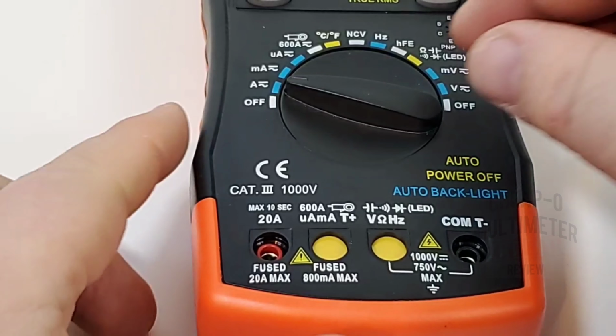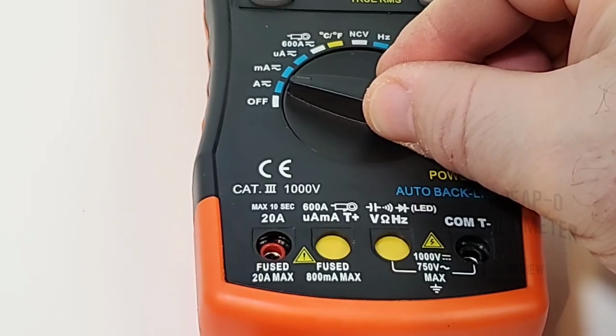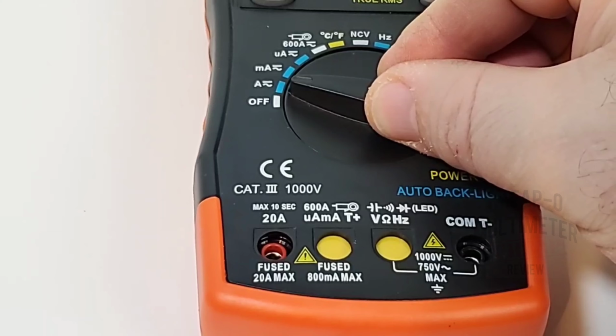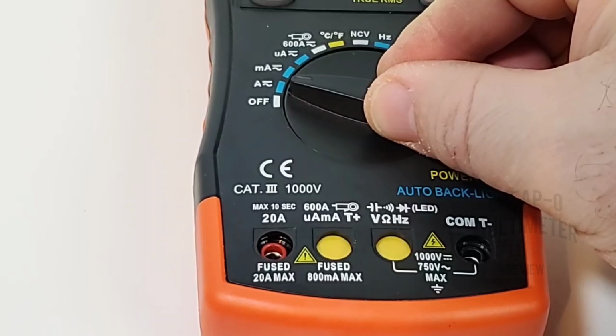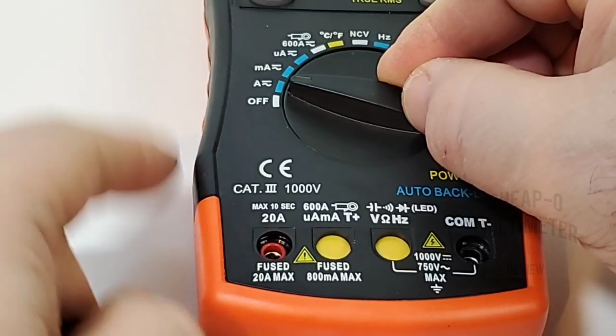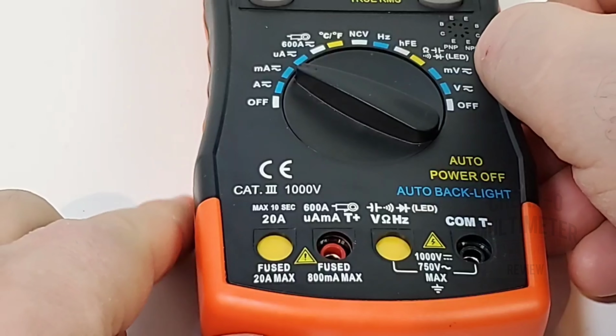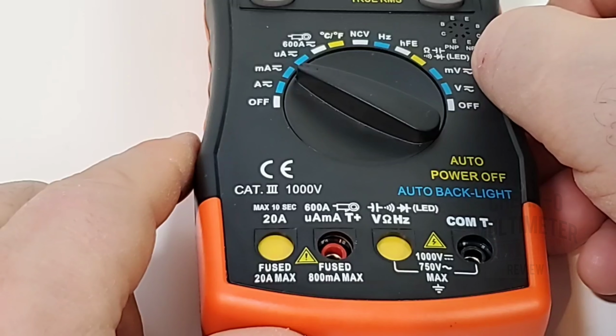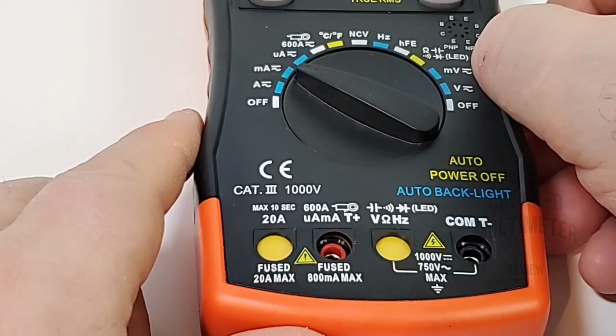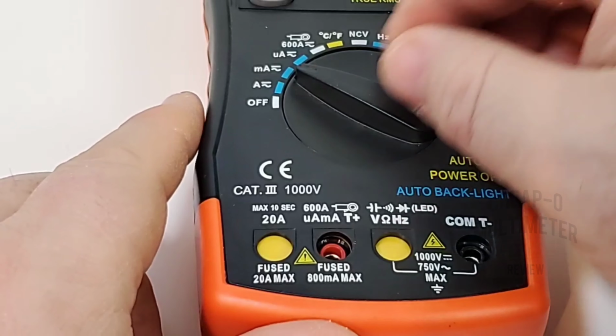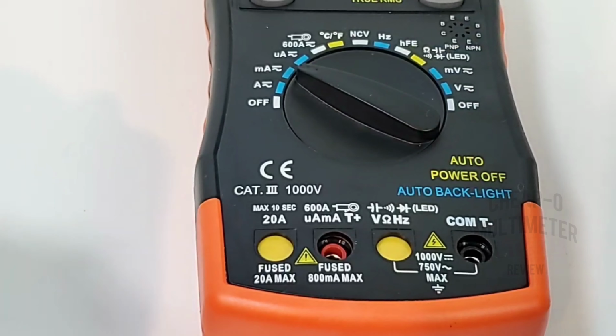Give you a quick look at those input protectors. Right now we're in high current amps, and you can see the high current input is exposed—20 amp input right there. Now when we go to milliamps, it blocks the high current input and enables the microamp/milliamp instead. Very cool.